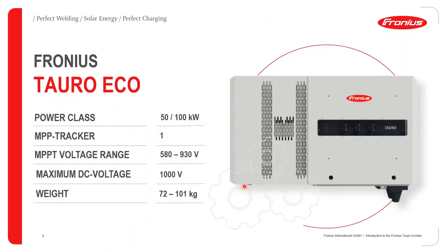If you're looking at further facts on the Fronius Tauro Eco, the power classes is either 50 kilowatts or 100 kilowatts. It has a single tracker. Your MPPT voltage range is between 580 to 930 volts. So again, you've got a very wide MPPT voltage range, which is really great for string planning. Also, your maximum DC voltage per string is 1000 volts DC. So for example, if you are going to purchase the 100 kilowatt Fronius Tauro, you can have 22 strings of 1000 volts DC connected directly to the inverter. Whereby if you go for the 50 kilowatt Tauro, you can have up to 14 strings of 1000 volts DC connected directly to the inverter.